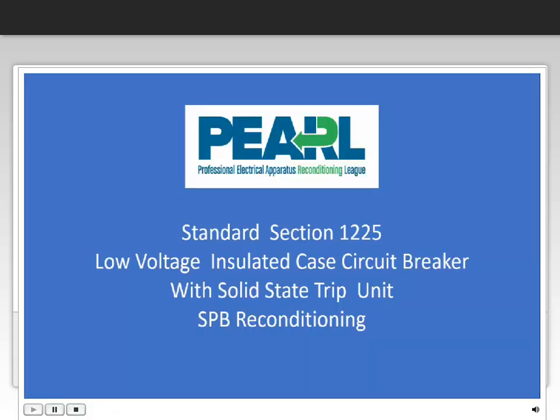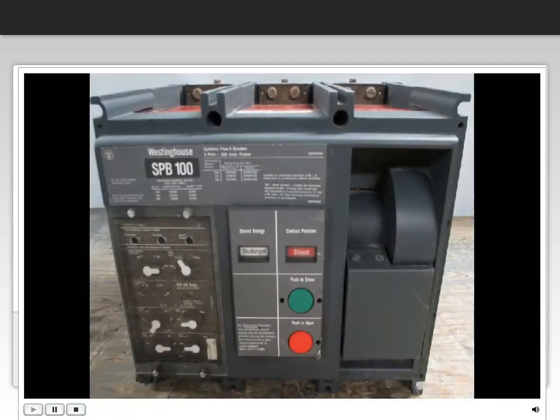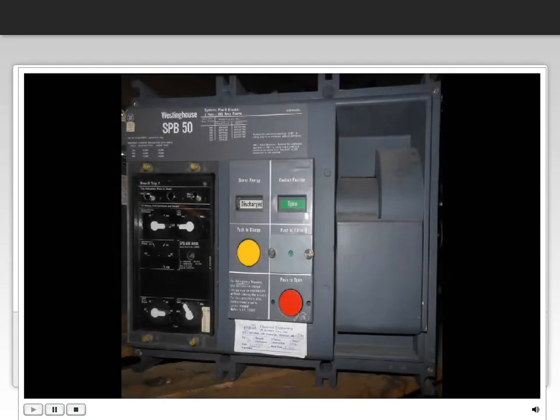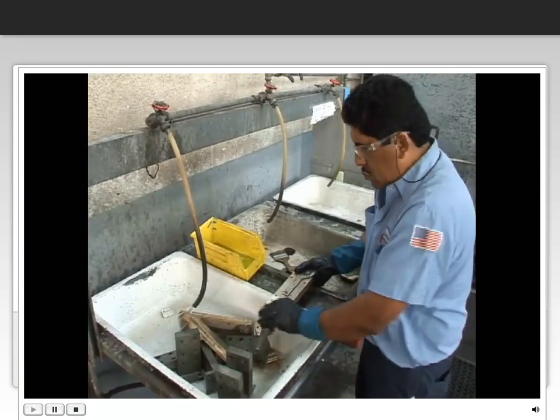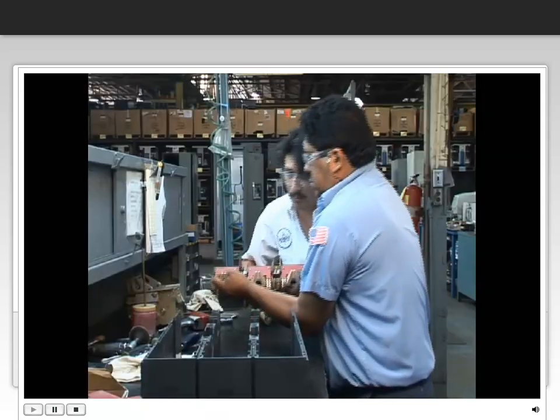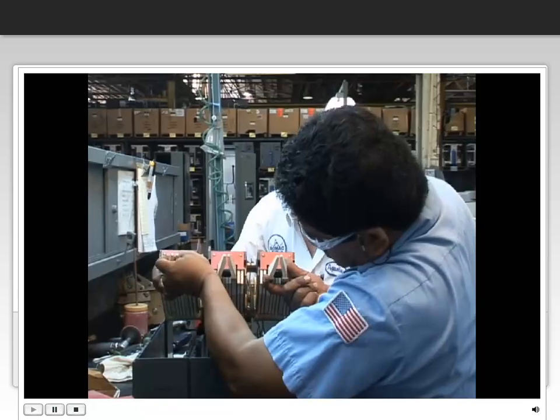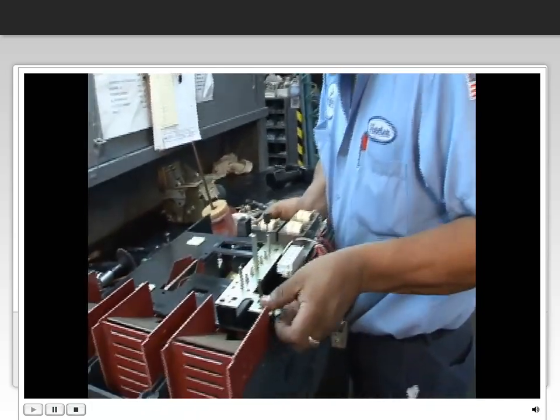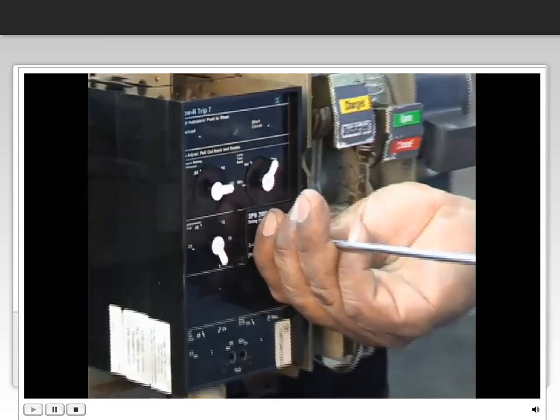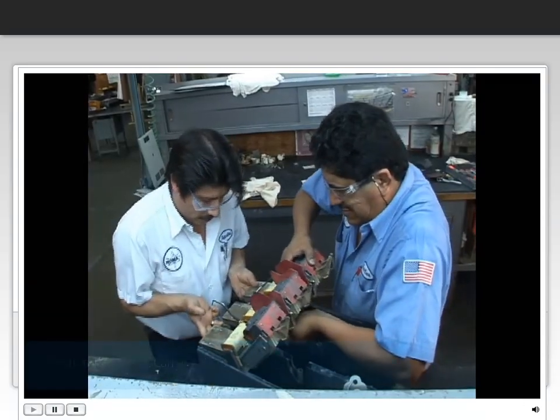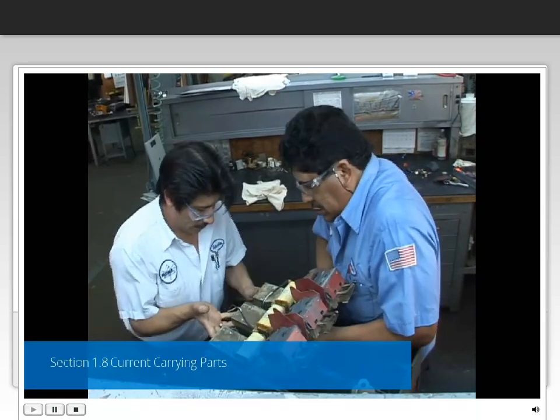Pearl Standard 1225 covers evaluation, testing, and reconditioning of low-voltage insulated case circuit breakers with solid-state trip units. This video shows a Westinghouse SPB breaker, or systems power breaker, going through the reconditioning process at ROMAC, an authorized Pearl member location. It is important to note that the standard section applies to many types of units. The video covers only those parts that apply to the SPB breaker chosen. Also of concern is that the reconditioning process is not sequential with the topic listing of the standard. We will, however, show a caption indicating the section of the standard occurring.